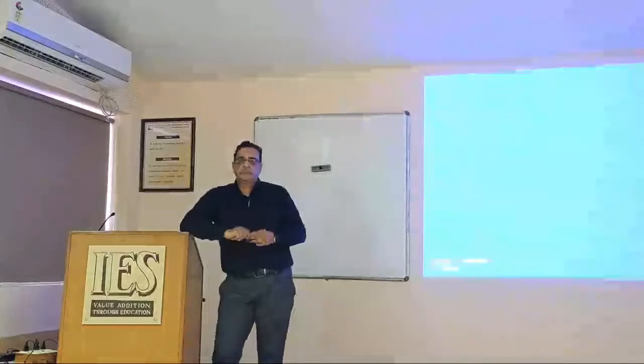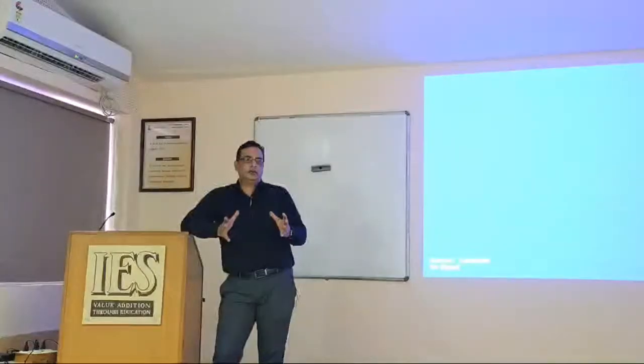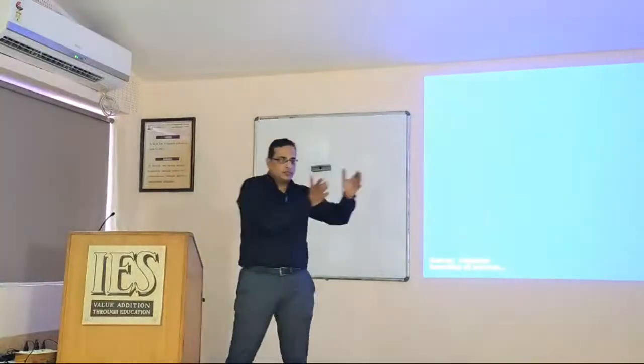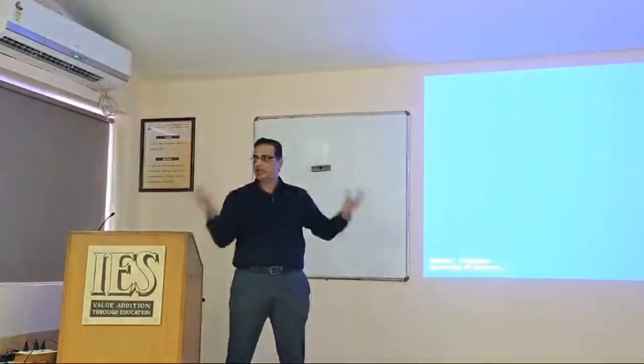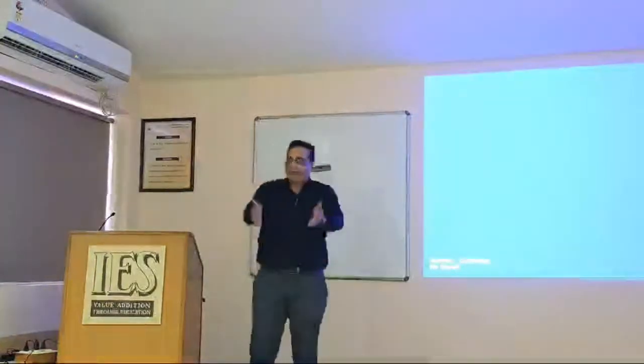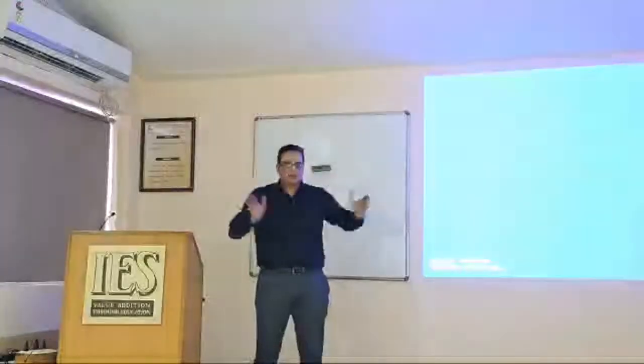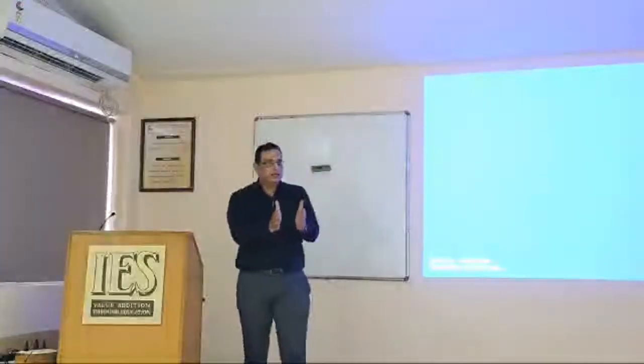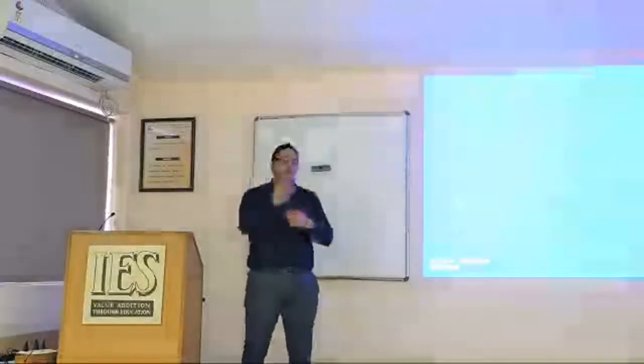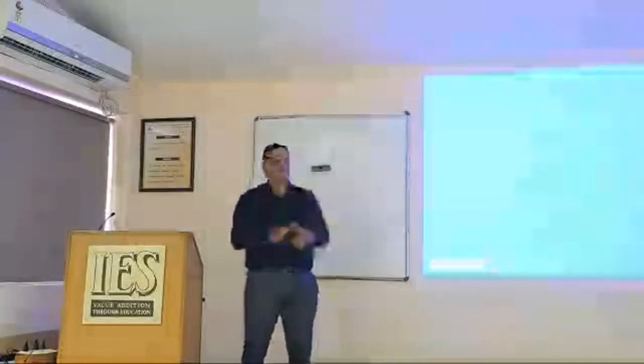So yes. And any shaft you are designing should be a minimum of 1 meter, because when we take a 1 meter shaft, some services will go towards either side of the shaft. So you have a 200 mm piping, say, on one side and 200 mm on the other side. Then you are getting a gap of 600 mm to go and service them. If you put a shaft compressed, the workmanship of our country is not that good. You need to work for the workmanship. The workmanship is not that great in our country, unfortunately. That we put a service and we fit and forget it.